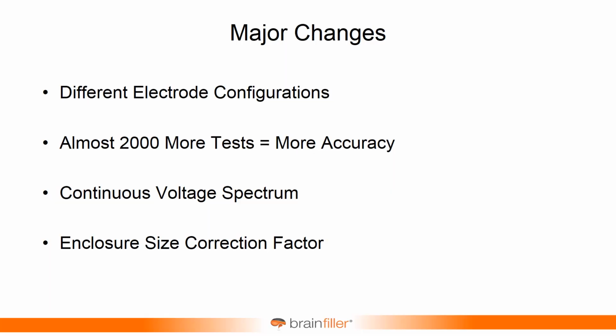So there are 3, but more than that, you interpolate along the way, because you're thinking, well, 600 volts, my system's at 480. That's still not perfect. Well, once you go through the calculations at 600 or whatever's appropriate for your system, then there's an interpolation that you go through to get this down to your actual voltage. There's also an enclosure size correction factor, because if you have an arc flash in an enclosure, the size of the opening is going to affect the energy. So we have more enclosure sizes or box sizes, but we also have an enclosure size correction factor to adjust if it doesn't happen to fit one of the enclosure sizes that we have.